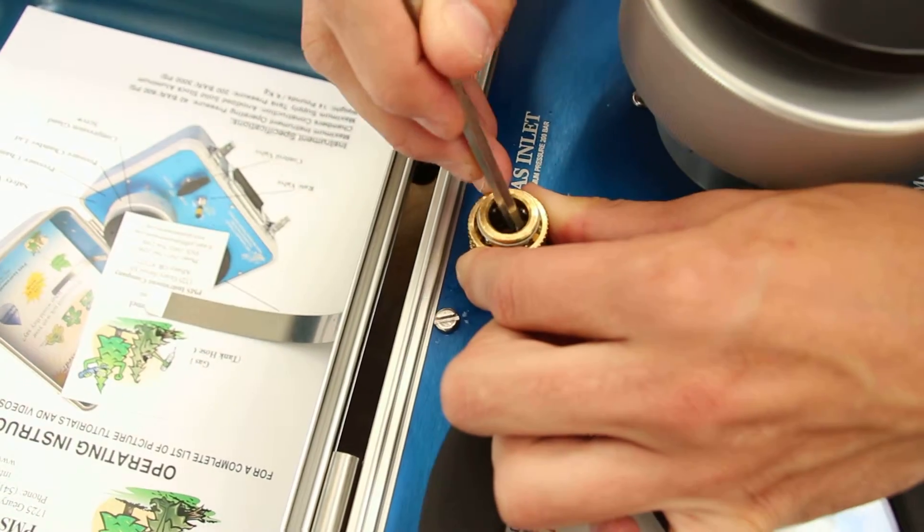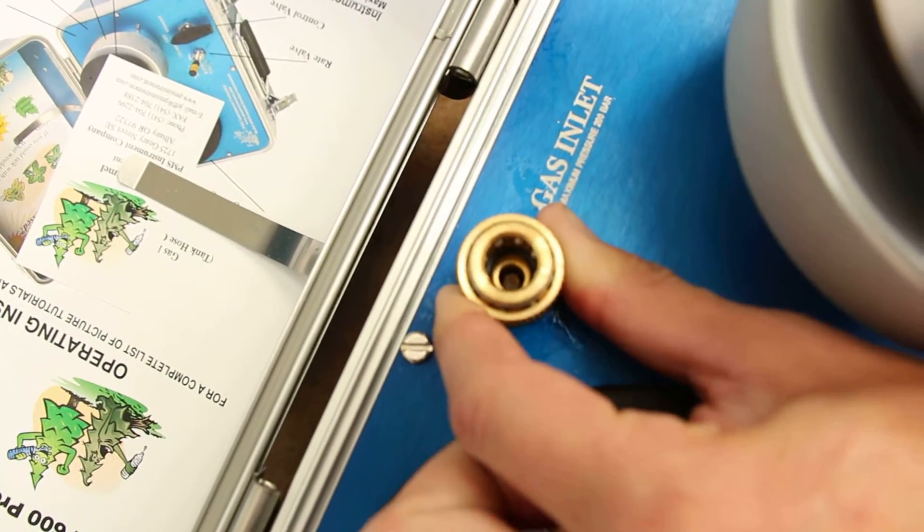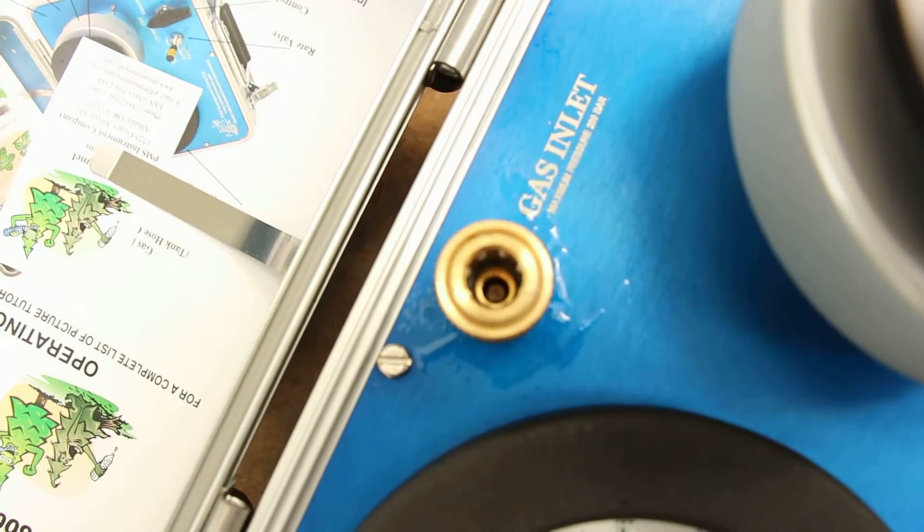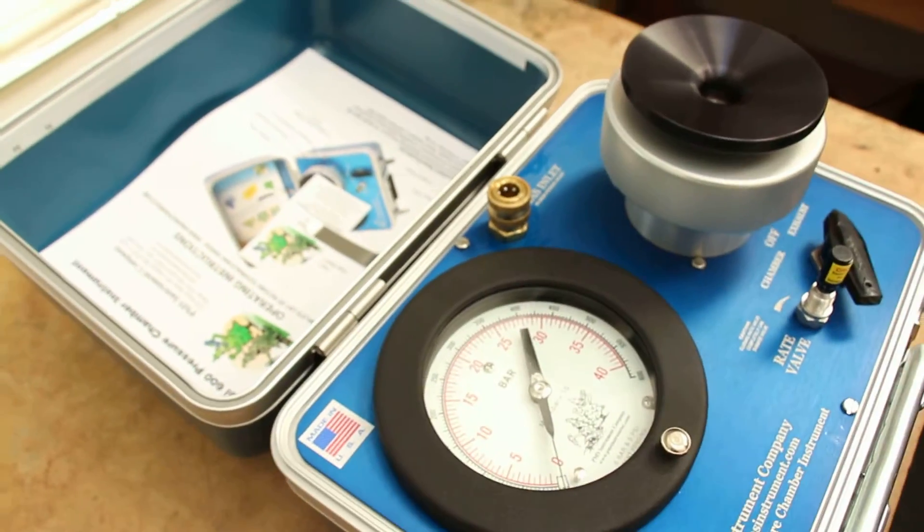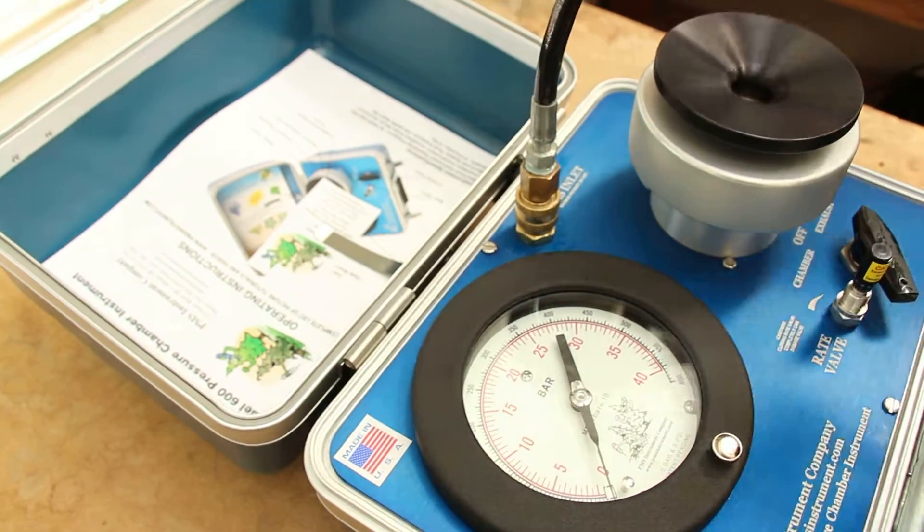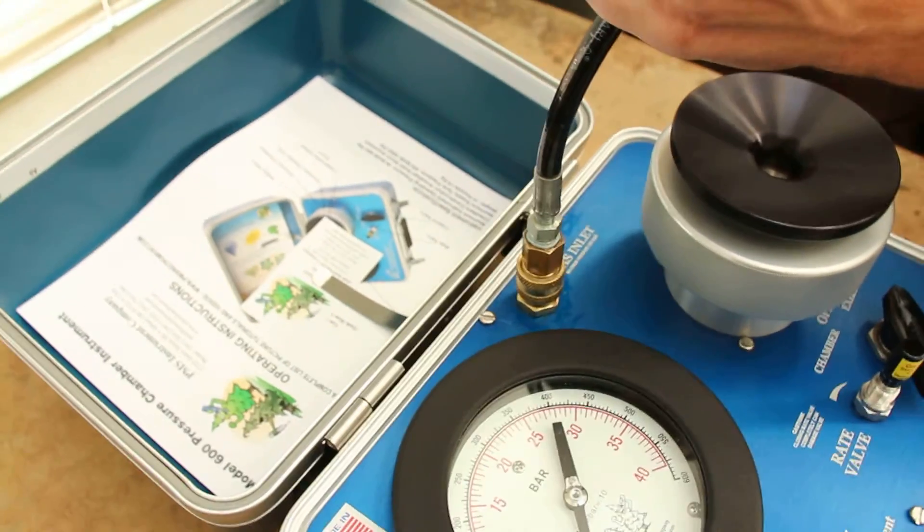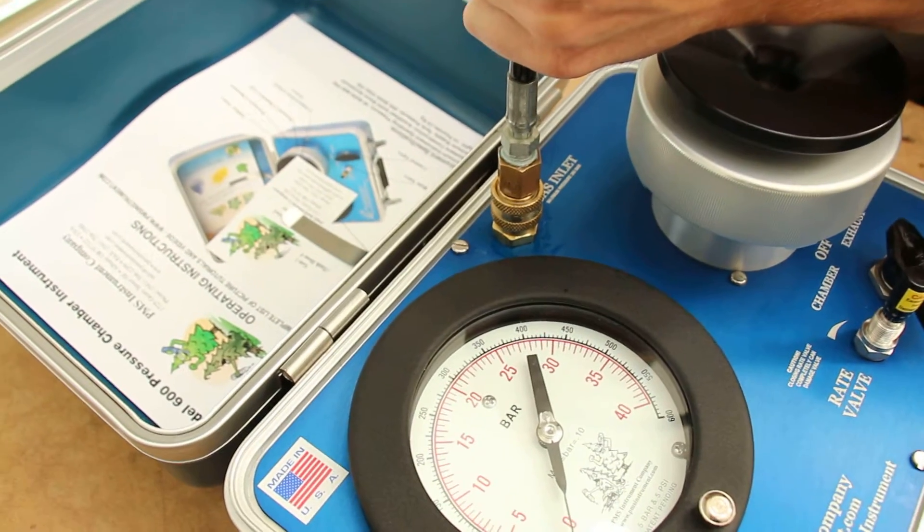So we're just going to slowly kind of work it around, and you'll know it's in there. It looks evenly placed right in there, and you can see, looking down this way, you can't even see the O-ring hardly at all. So then we're going to reconnect the instrument to that, make sure the muffler's turned off there, and then we'll pressurize it again.